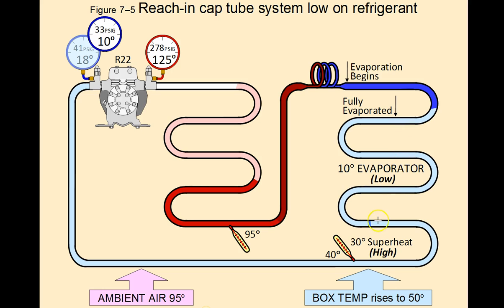In a normal system, we would have the refrigerant changing state all the way down to the very end of the evaporator coil, and then we would pick up superheat right at the end — that would be the normal operating condition. But in this undercharged condition, everything boils off early, and we have all of the remaining evaporator coil in which to pick up superheat.